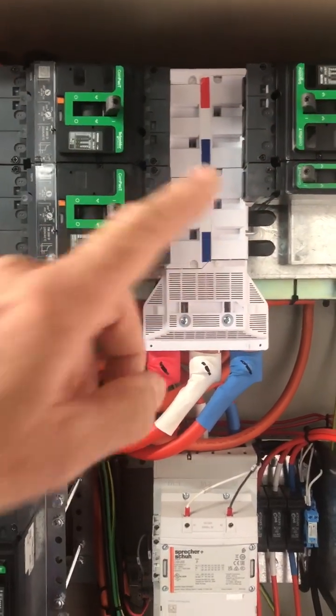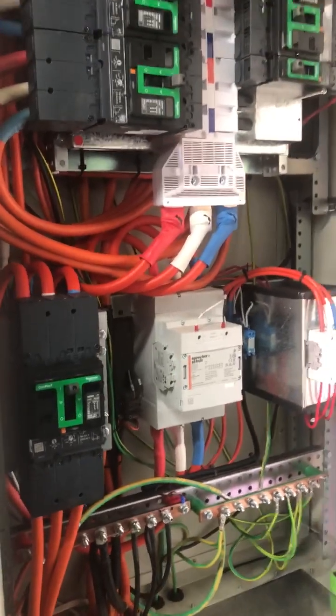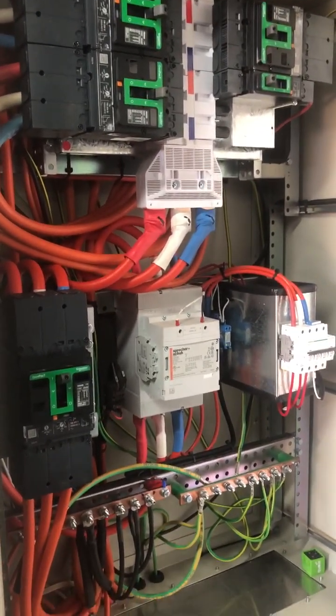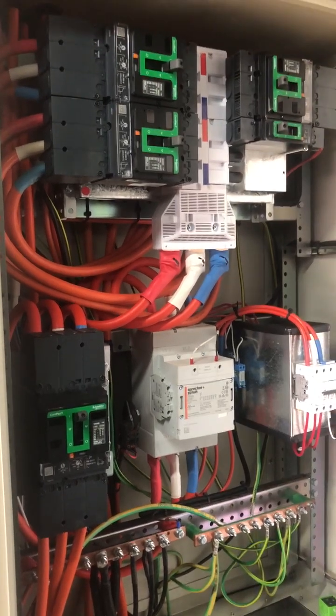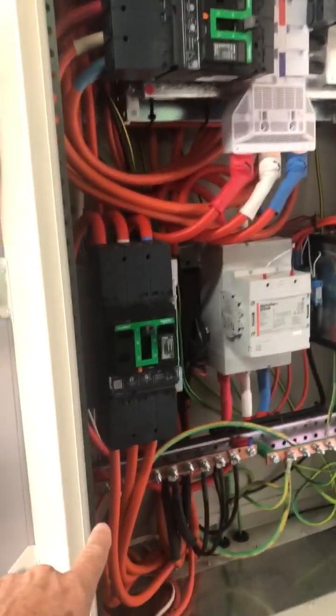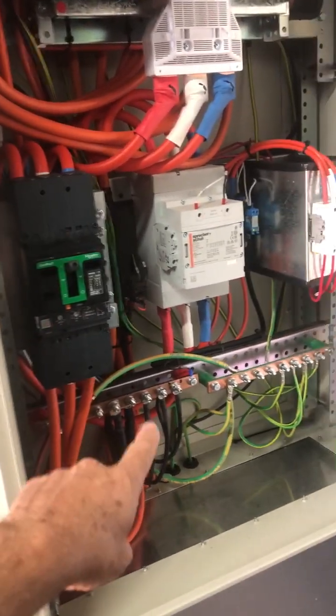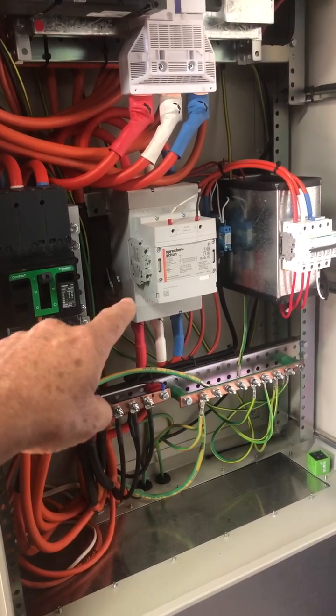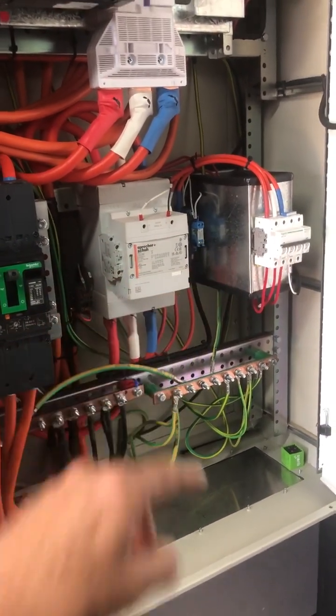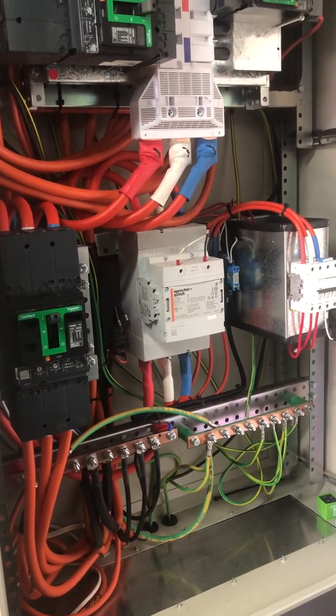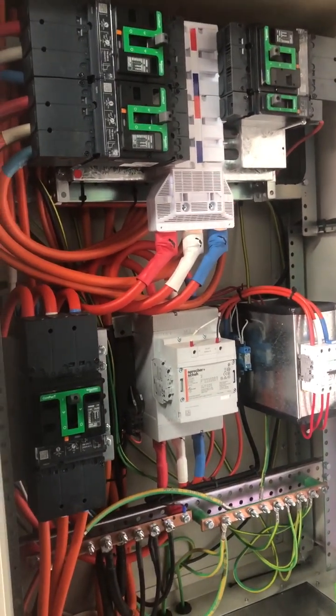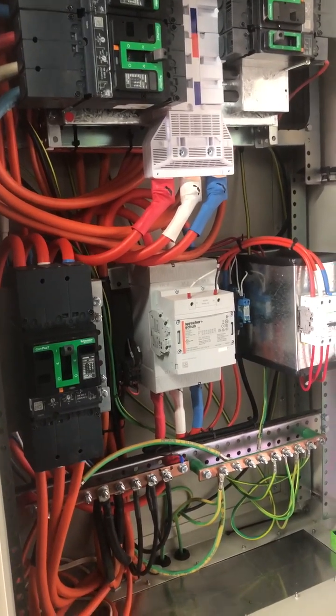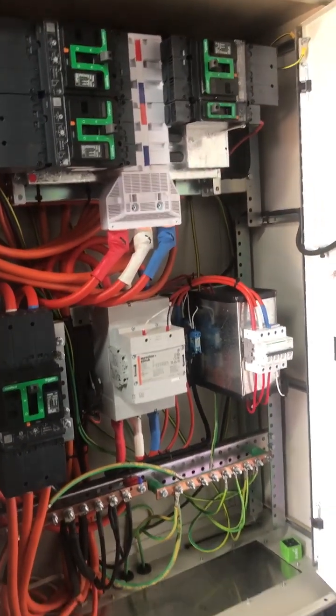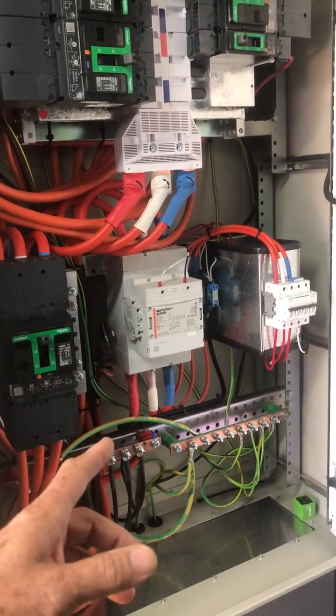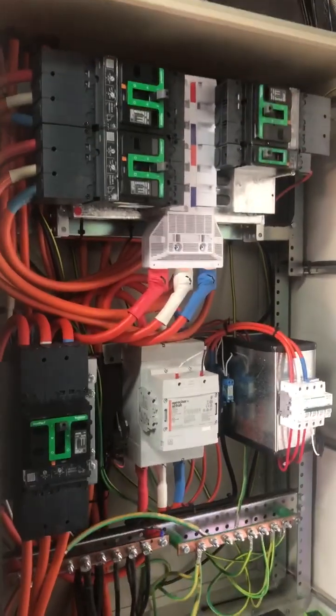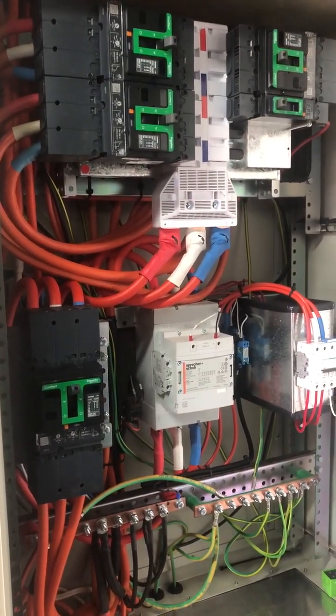So you call this an AC coupled system. What happens is, if the programming of the multi-mode inverters calls for a generator, the generator will start, and it becomes live on the line side of the contactor. There are some sensing devices that inform the multi-mode inverter that there's power there, and then it begins to synchronize. We have to have a synchronization between the inverters that are operating and putting energy into the site, and the generator. The sine waves need to synchronize. If they don't synchronize, you'll have a bit of a disaster here.